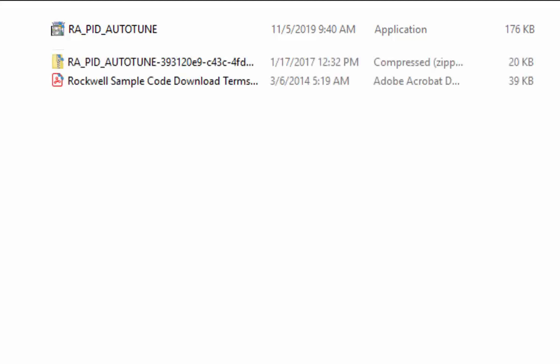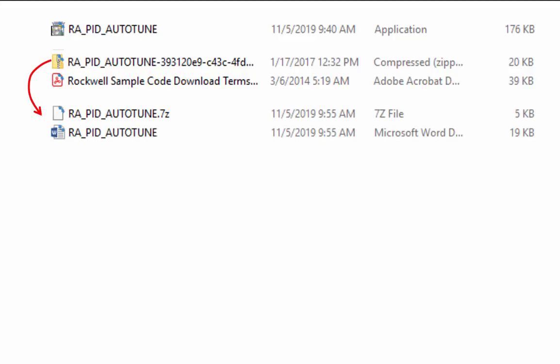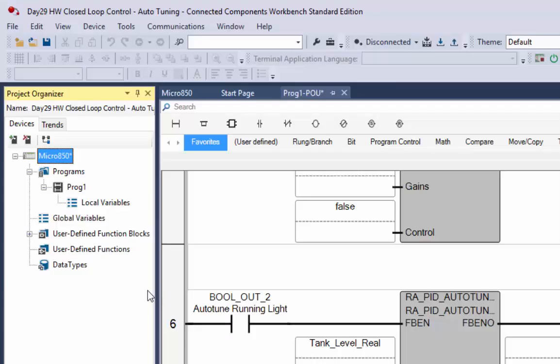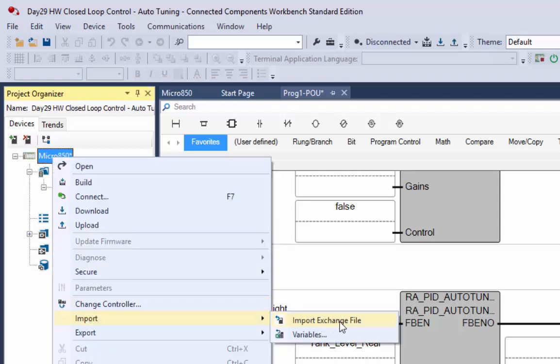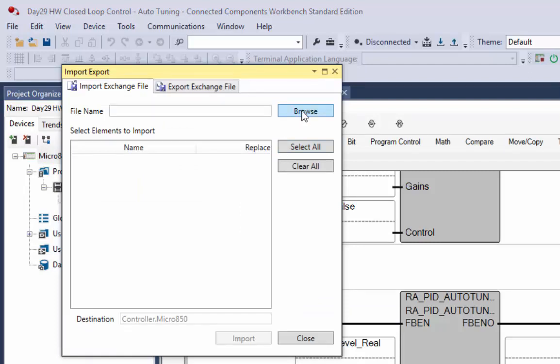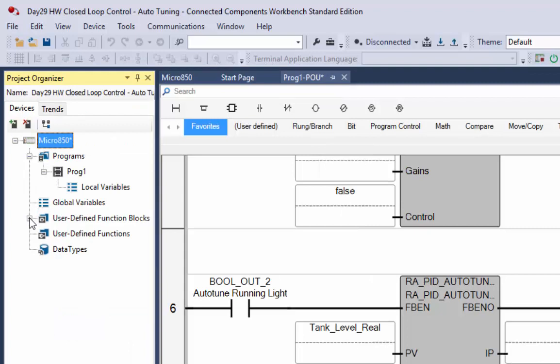If you double-click and run the application, you'll see that all it does is extract two files — one is a zip file and one is the terms and conditions of use as a PDF. You'll then have to extract the zip file and you'll get two files: one is the RA_PID_AUTOTUNE.7z file, which is the user-defined function block, and the other is a Word document with information on it. You can then import that user-defined function block into Connected Components Workbench by right-clicking on your Micro 850, selecting Import, and importing an exchange file. Once it's imported, you'll see it show up under user-defined function blocks.